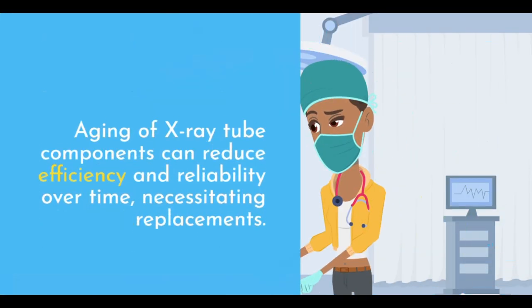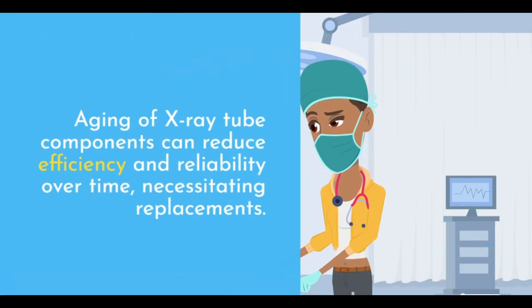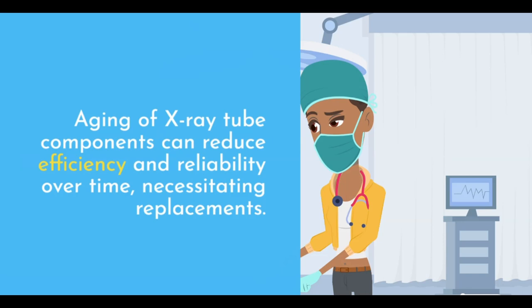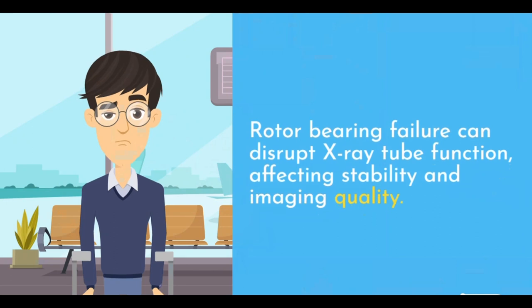Aging of X-ray tube components can reduce efficiency and reliability over time, necessitating replacements. Rotor bearing failure can disrupt X-ray tube function, affecting stability and imaging quality.